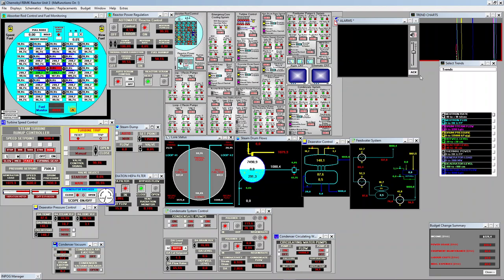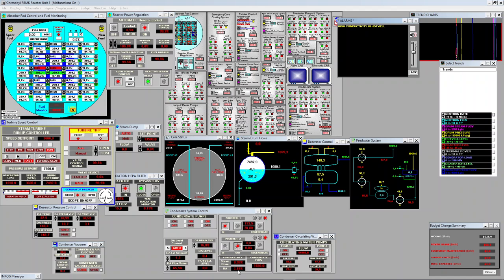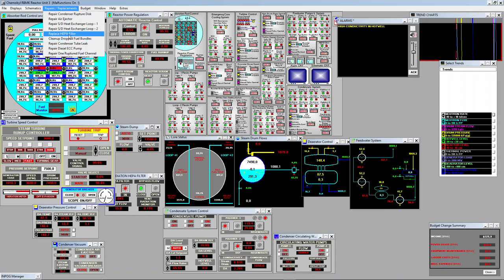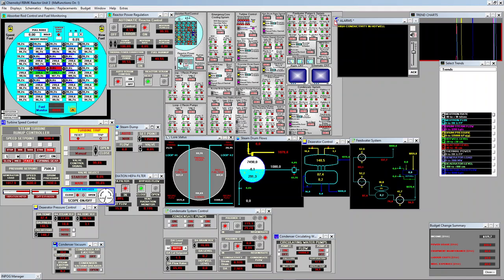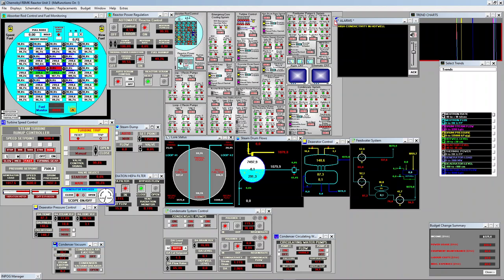High conductivity in the hot well. Let's see. Conductivity is increasing, it's at 2.19. If we have conductivity in the hot well, it must be that we have a leak in the condenser tube leak. I don't know if it solved the problem, but we'll check back the conductivity in a while. It's already decreasing, so I guess it was the problem.